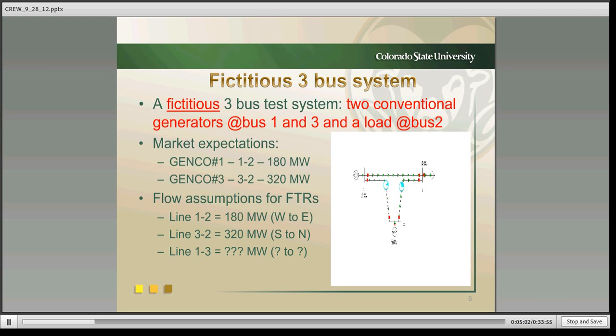So it essentially mentions a single path, but due to the interconnected nature of the network, there will be multiple paths. FTRs here stand for financial transmission rights. In the market, at line 1-2 for this transaction, we allocate about 180 megawatts from west to east, and from south to north about 320 megawatts on this line, which is the direct flow. This snapshot was taken after the power flow converged, and we can see there is flow on path 1-3, which has no allocation as far as the market is concerned—yet there is power flow on that line. This is the most elementary example one could provide to show what an unscheduled flow looks like.